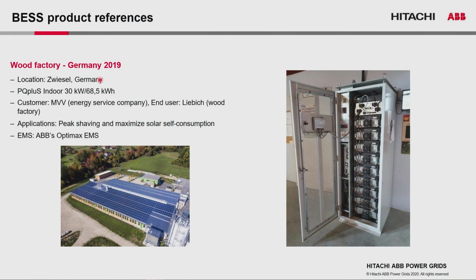This is a sawmill wood factory, also in Germany, where we also have a massive solar roof. So for the peak shaving, here the utility didn't accept it. In Germany, you need to have the auto consumption as much as possible, otherwise you pay a huge penalty. And here we installed 30 kilowatts, 68 kilowatt hour to maximize the self-consumption and avoid the peak. So this is very similar to the distribution center, but in industry. And here it was a relatively compact solution, one cabinet indoor.